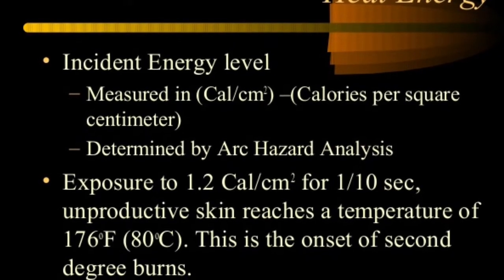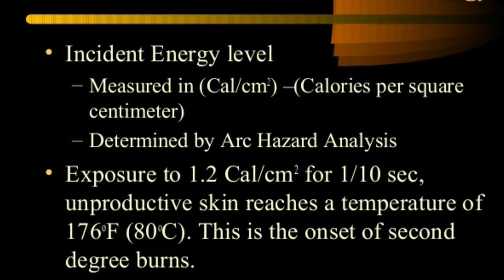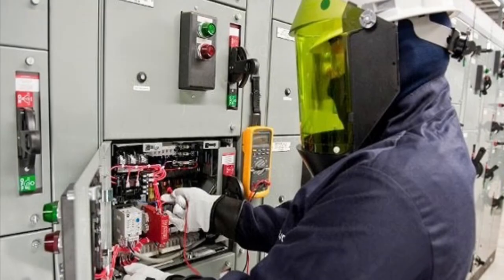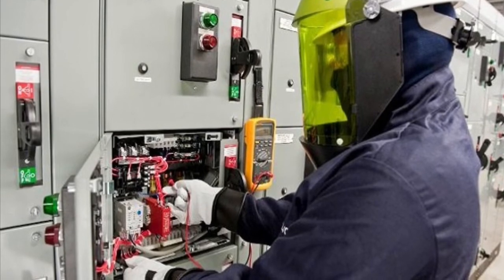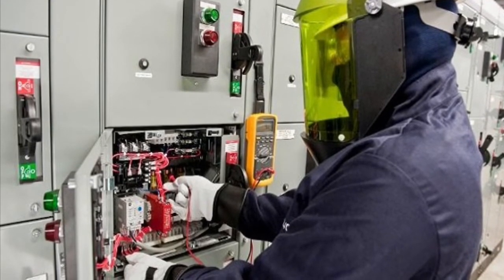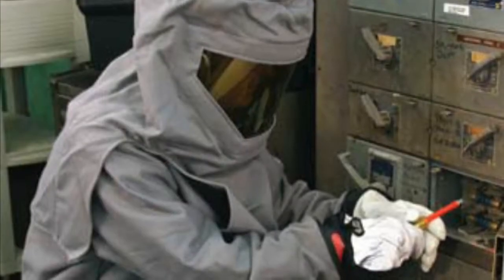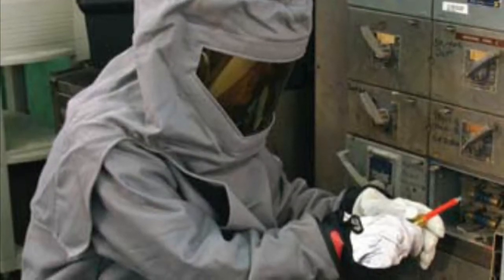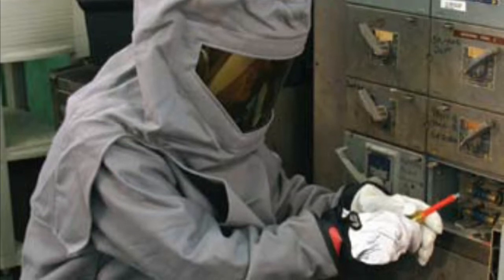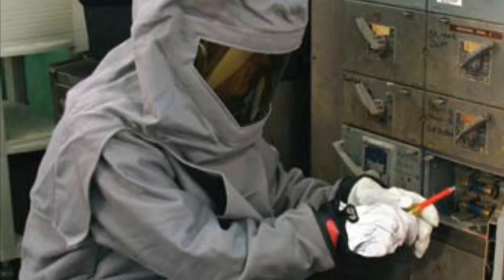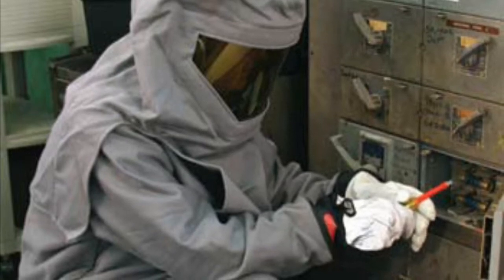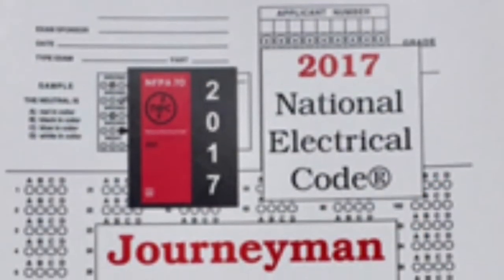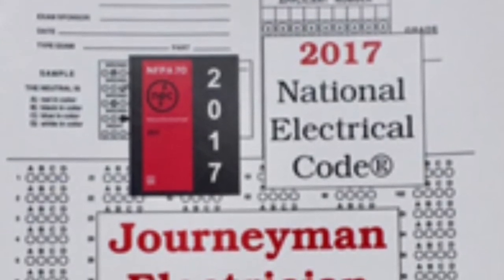Using PPE rated above the calculated incident energy value can raise the probability of the employee being protected. A qualified person is one who has demonstrated skills and knowledge related to the construction and operations of electrical equipment and has received safety training to identify the hazards and reduce the associated risk. An employee could be qualified to perform one work task and not qualified to perform a different work task on that same piece of equipment, or qualified to work on one piece of equipment but not another similar piece.